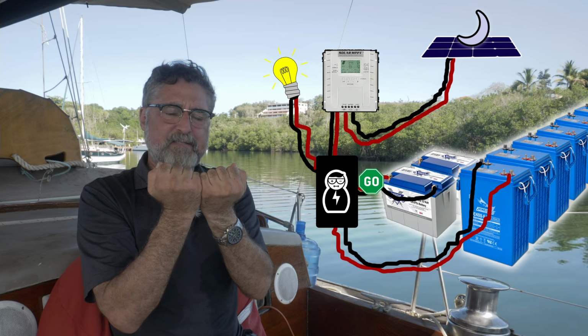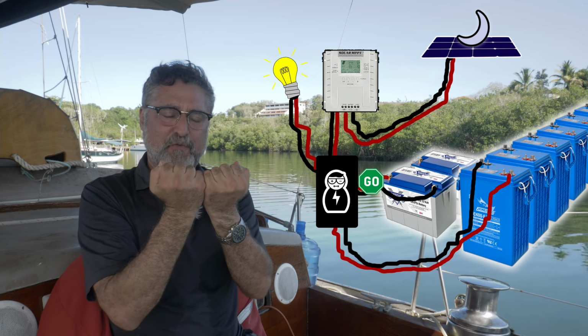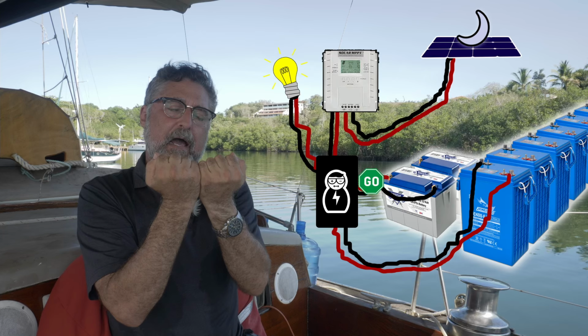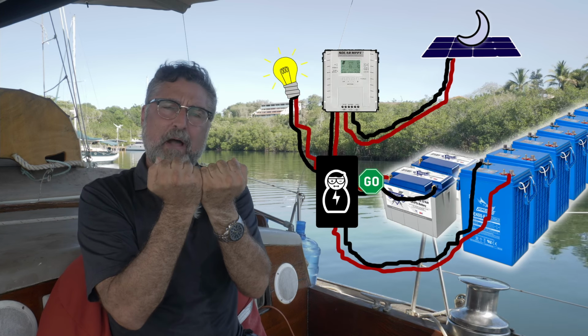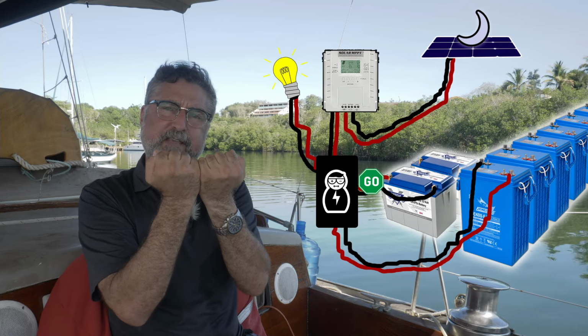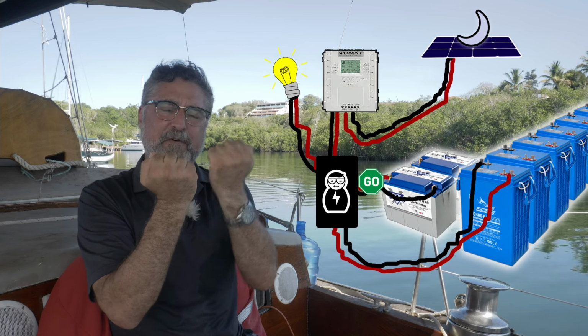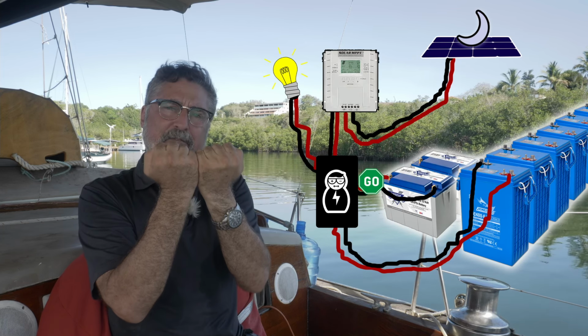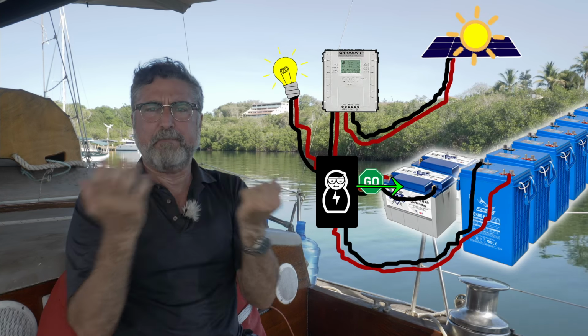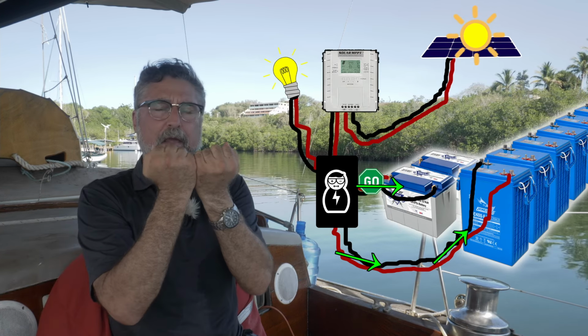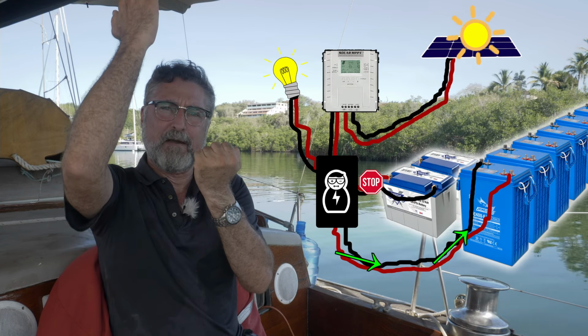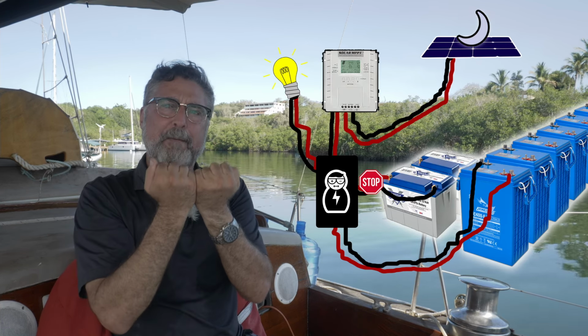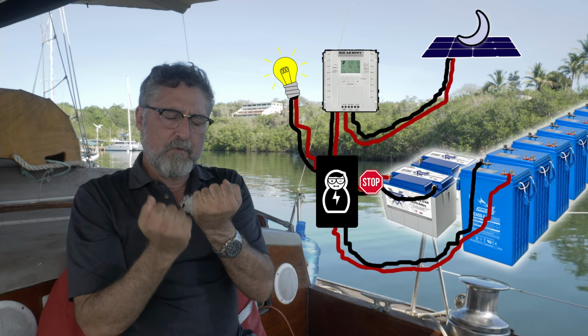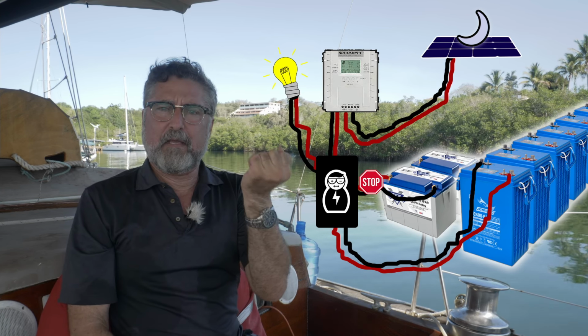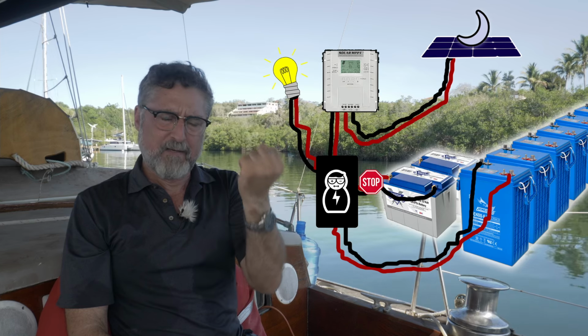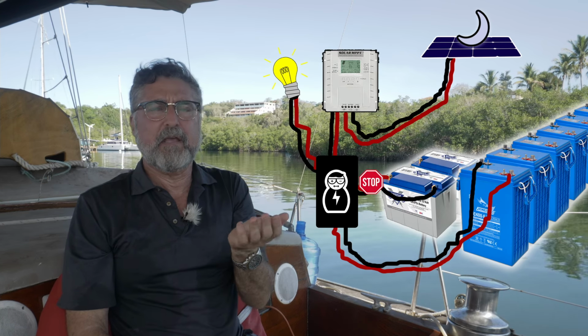A couple things my system does beyond that, which is pretty useful: it watches, and if it's marked the batteries as fully charged in its memory but charging starts happening again - because that drop could just have been a big cloud that came over - it'll drop the lithium off, let the lead come up, and wait till the next cycle to grab it. It won't mark the lithium as a candidate for full recharging until it's come down to a lower voltage.